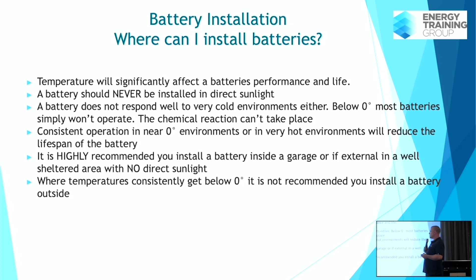I, again, highly recommend you're installing them in garages wherever possible. This is an example of a battery we installed outside, and we built a little house to keep it out of the sun. You can see that the top and the front is protected from the sun, and it's only open on the outside, right? So it's got plenty of airflow, but we're keeping direct sunlight off the battery. And an eave isn't going to achieve this, right? An eave's up high, your battery's down at ground level, so generally an eave isn't going to provide enough shade to protect your battery.